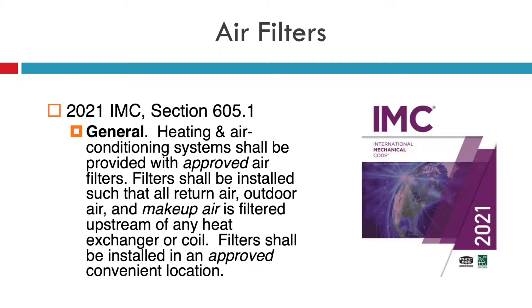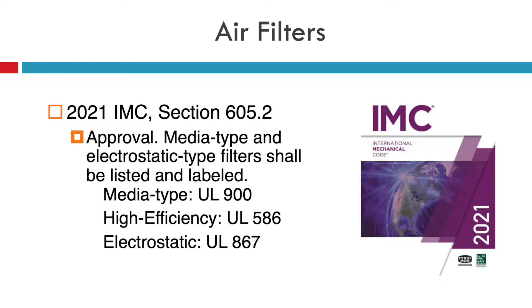Filters shall be installed in an approved, convenient location. Regarding approval of filters in Section 605, media type and electrostatic type filters shall be listed and labeled. If they're media type, they need to meet UL900. High efficiency filters need to meet UL586, and electrostatic filters need to meet UL867.